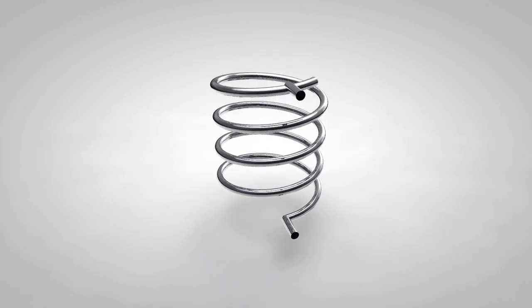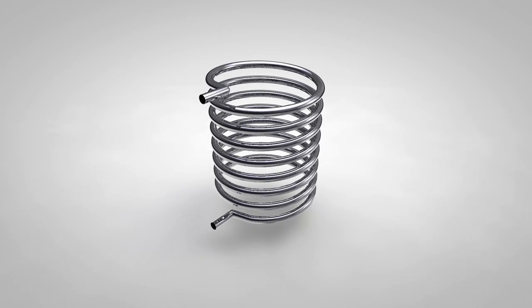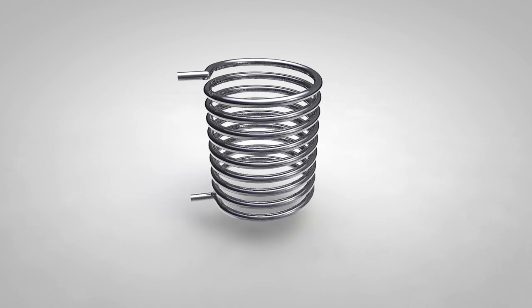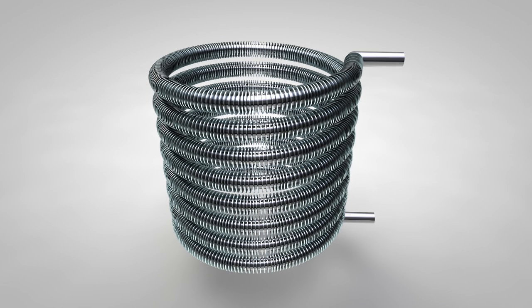Having a large coil surface area and a high kW rating is important for heat pump cylinders because they work at relatively lower temperatures compared to a conventional boiler, meaning the coil needs to transfer as much heat as possible.